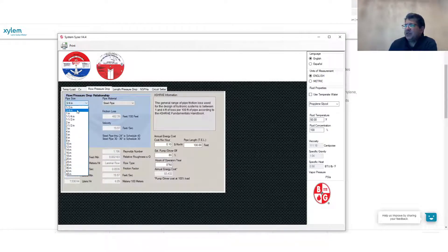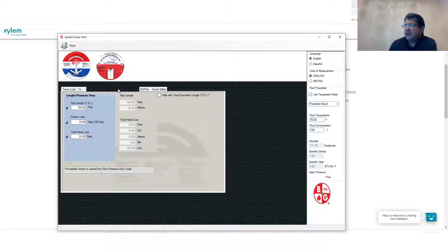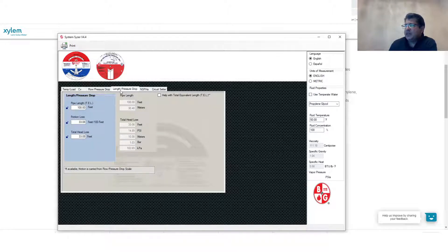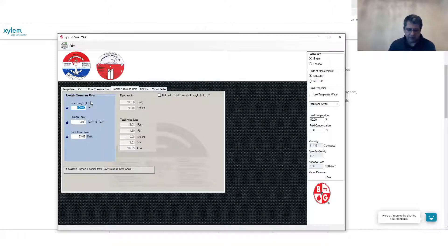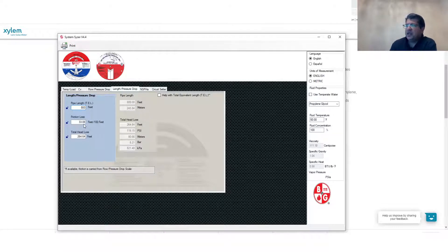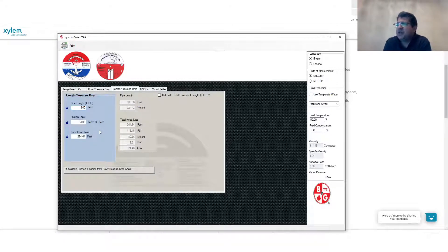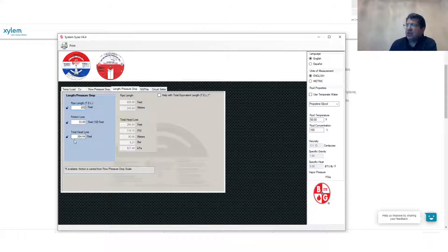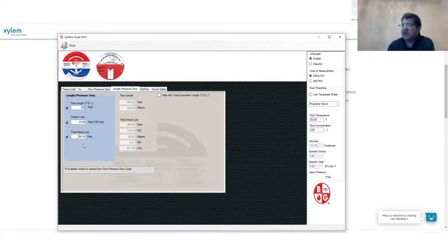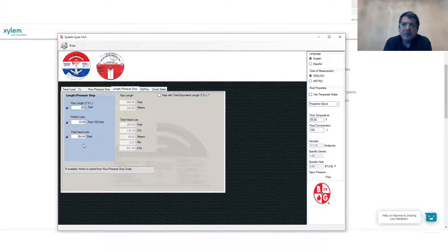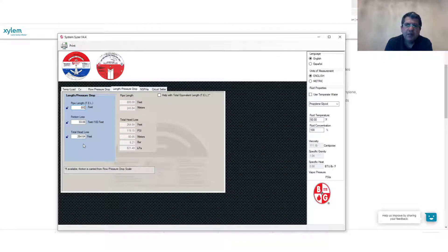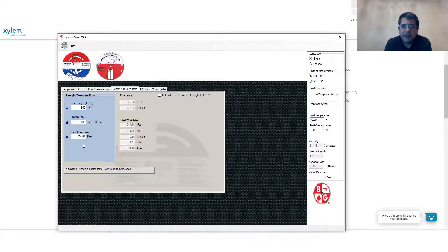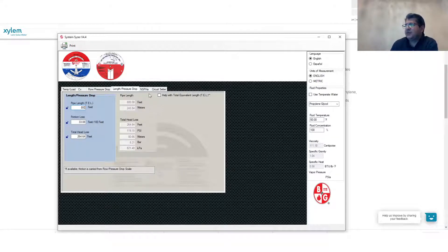Going with the same parameters to the next tab. If I'm changing this back to say one and a half inch, if I go back to my second tab, which is length pressure drop, and I input if my pipe in my entire building is say 800 feet as a whole, with the 33 feet per 100 feet of friction loss, I'm looking at a total head of 264. This is a number that we get. And when we add the effect of our other features, such as the feeding to this, we can come up with our total pressure drop, where it helps you to select and size your pumping that needs to distribute the hydronic into the system.